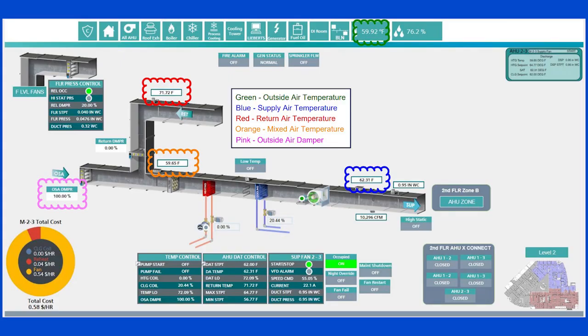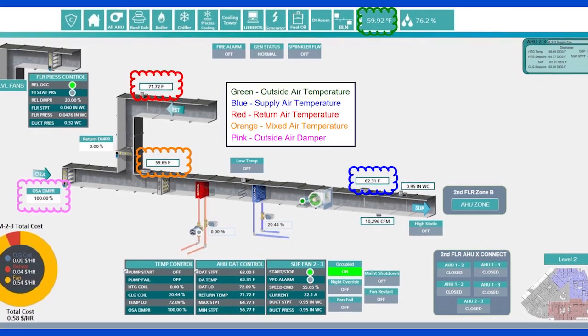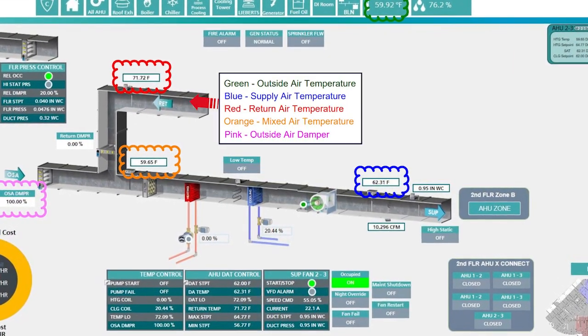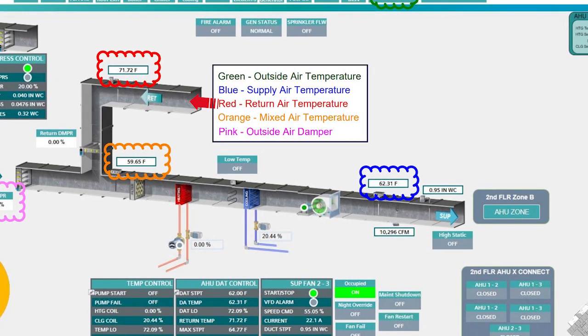Next, let's look at some examples of economizer trends in different scenarios, both functioning and improperly functioning. First of all, let's orient ourselves back toward our air handler. This is a diagram from the BAS system of the air handler. So, of course, you can see here your return is in red, and that is feeding into the mixed air, which is in orange, and we also have the outside air coming in here to the mixed air chamber. We then have our heating coil, our cooling coil, and flowing on through to the supply duct.